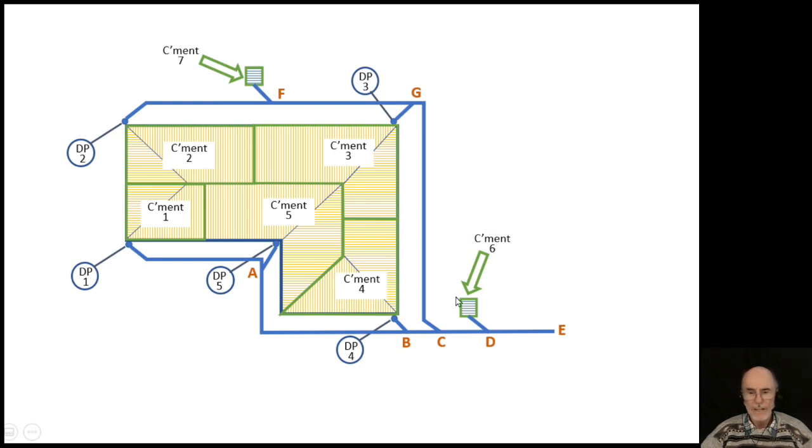Only one catchment area is allowed per inlet structure, so whatever's going into there is combined all in one big catchment area. Our inlet structures are given a name, and the important thing here is it must start with a letter and end with a number. It can be anything. This could be gully pit 1, field inlet 1, or A1, B1, whatever you like. It must start with a letter and end with a number.